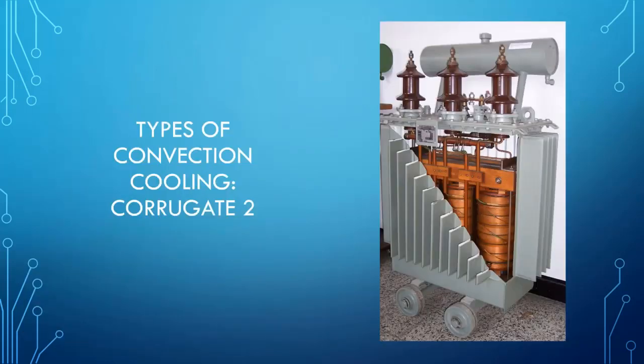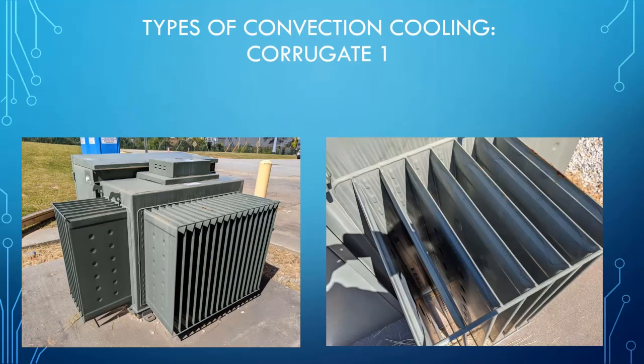Here's another example of corrugate. And what you're seeing in this picture is that those fins are hollow so that the oil can move through those fins. It comes in the top, goes down through the fin, and then comes back into the tank at the bottom of the fin. In the process, the heat will evaporate out of that fluid and it will return to the tank cool, and then the process starts all over again.